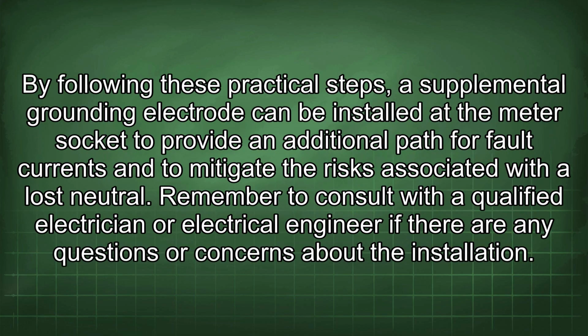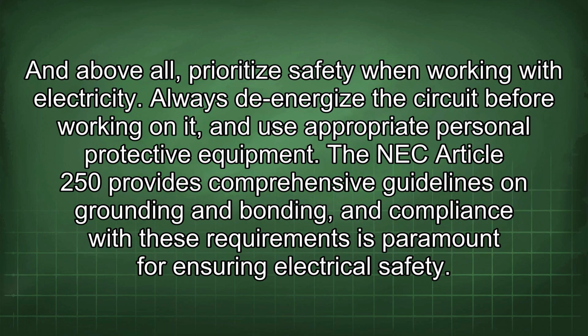By following these practical steps, a supplemental grounding electrode can be installed at the meter socket to provide an additional path for fault currents and to mitigate the risks associated with a lost neutral. Remember to consult with a qualified electrician or electrical engineer if there are any questions or concerns about the installation. And above all, prioritize safety when working with electricity. Always de-energize the circuit before working on it, and use appropriate personal protective equipment.